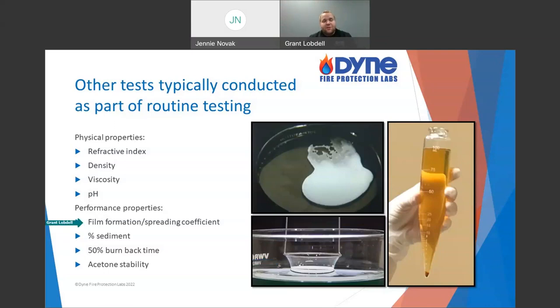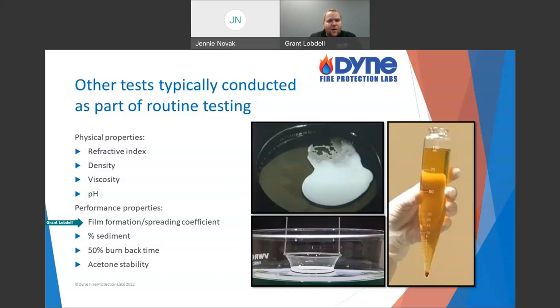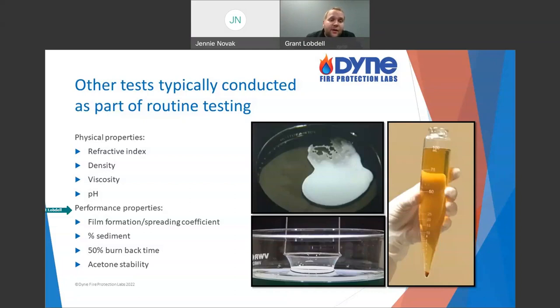I put film formation right up there with expansion and drain time for film-forming foams. If a foam sample comes to our lab with great expansion and long drain time but doesn't form a film, and it's listed as an AFFF — it's still going to fail. It's supposed to be an AFFF with that added layer of protection, and if it doesn't have it, it fails. Those are what I call performance properties.